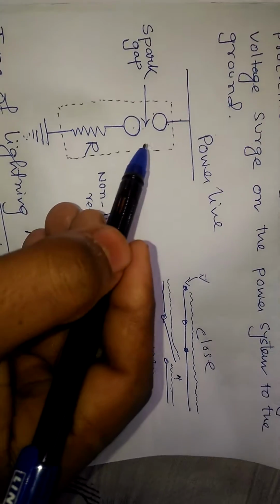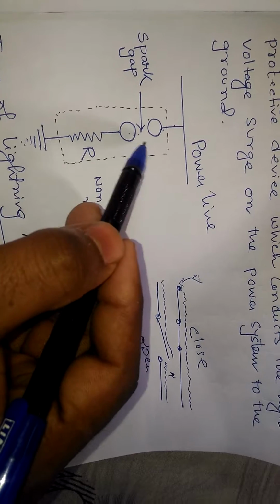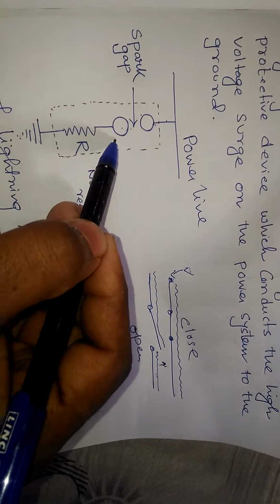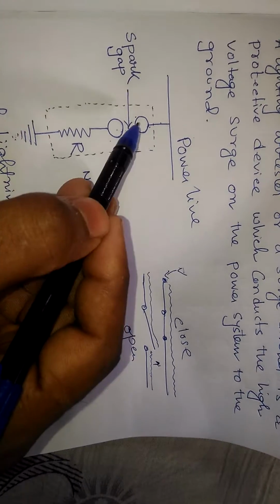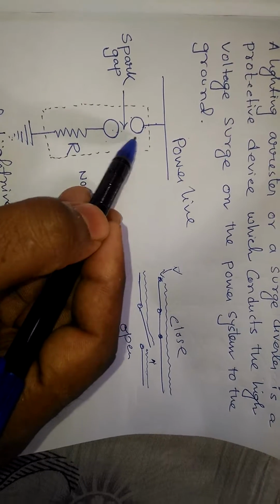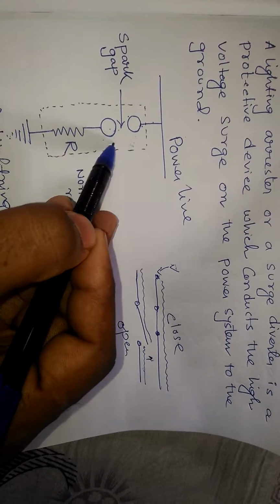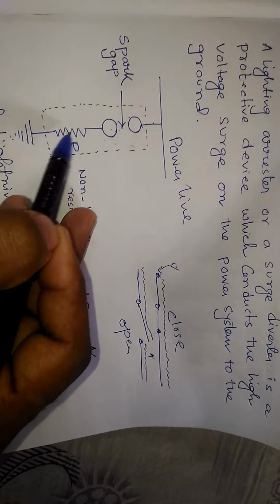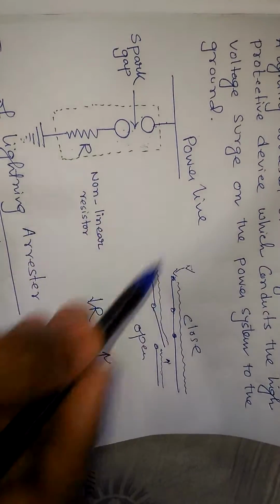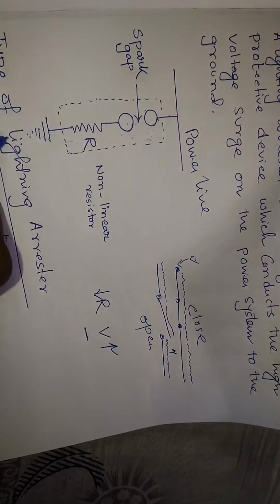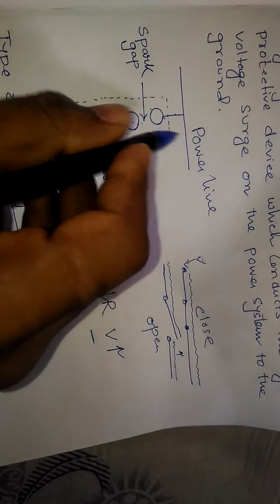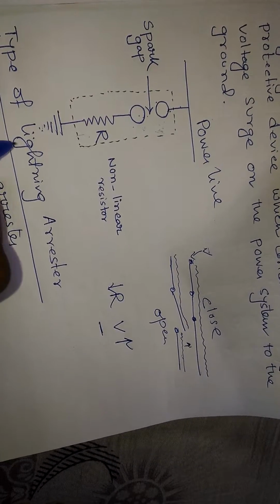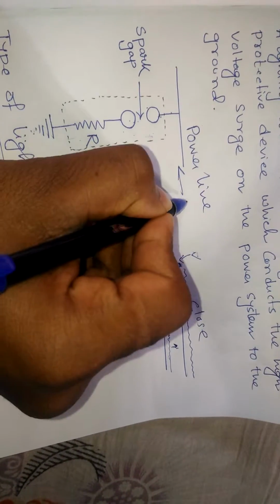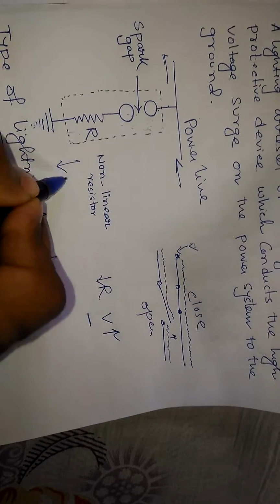So you have to remember that during normal operation, this gap is non-conducting, and in case a high voltage or surge is injected into the line, or a surge is just coming to the line, the gap will break down and the high voltage will be passed through this. And then if the voltage is higher, the resistance will be lower. It is a low resistance path, so the extra charges will be grounded. So these extra charges will not be injected into the line. If the line is coming from this direction and going in this direction, the extra charges are grounded here, and then the normal voltage will go in these directions.